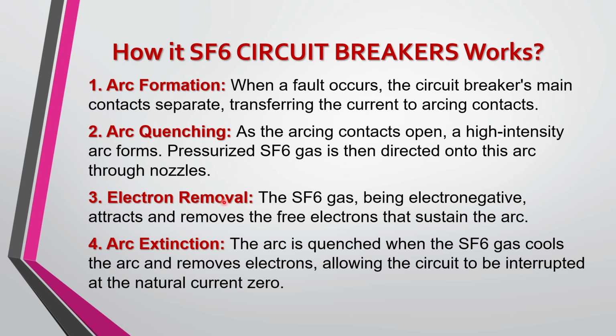Next is electron removal. The SF6 gas, being electronegative, attracts and removes free electrons from the arc that sustain the arc. So, because it absorbs the free electrons, the arc extinguishes rapidly, as its free electrons are absorbed very quickly by SF6 gas. So this property of SF6 gas makes it very much suitable for this type of high voltage circuit breakers.